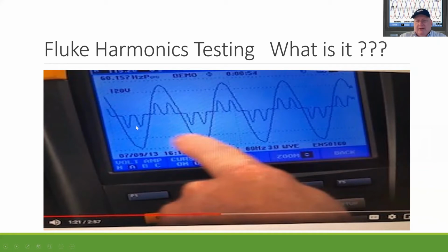Well, like here, where you're getting, this is on a 60 cycle power input, you'll see this one, this one, this one, and this one. Well, all of a sudden, that creates 120 hertz ripple voltages on your circuit in current. So you get 120 hertz noise. Well, as you speed up, slow down, all this stuff, these dips and ripples will go all over the place. And so you'll get a lot of this rippling in here. That's what they're talking about with harmonics. They're talking about the current harmonics, which, depending on the strength of the transformer and the power out there, will determine how much these dips are going to affect the voltage.